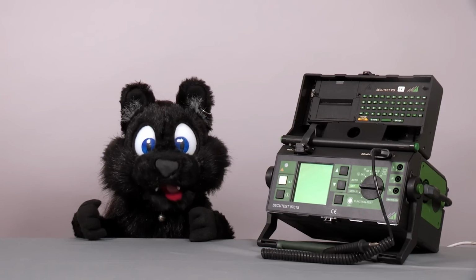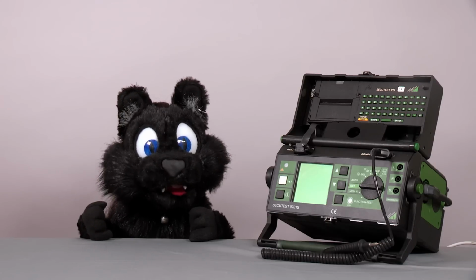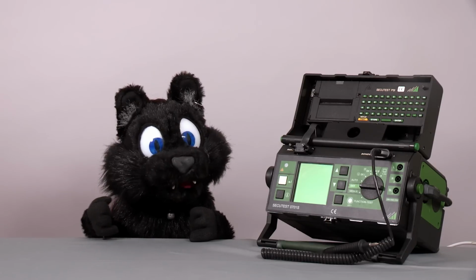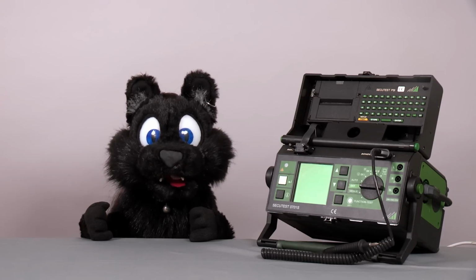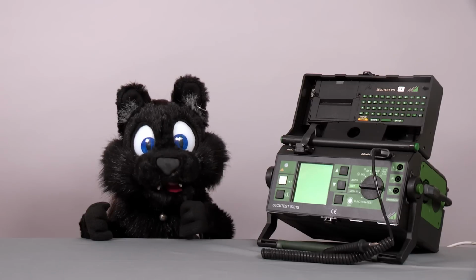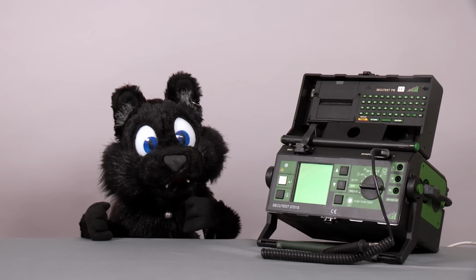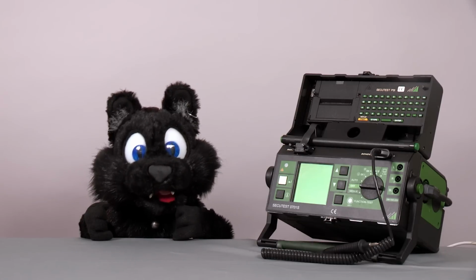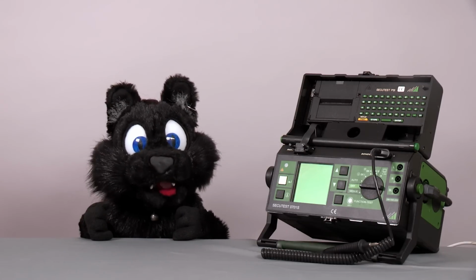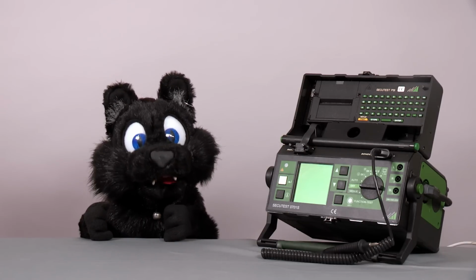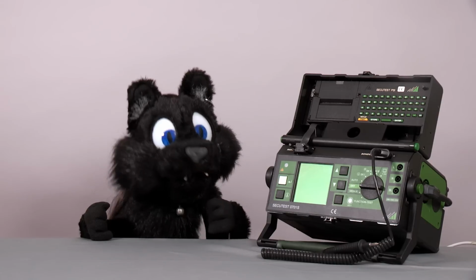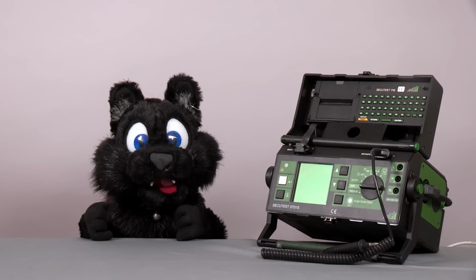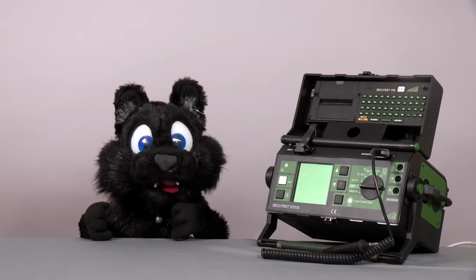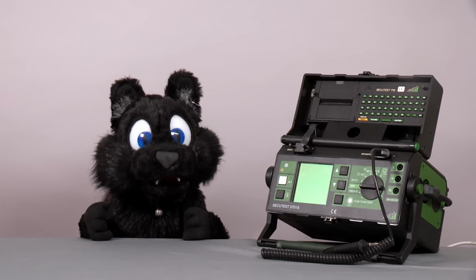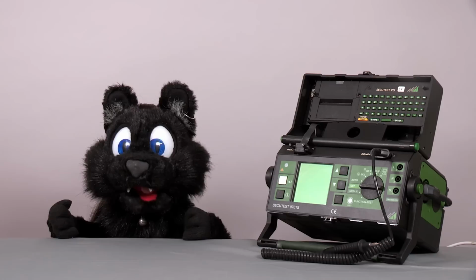In Germany, and therefore most likely similar in most of the EU, electrical appliances that are used in commercial settings like offices, hotels, shops, etc. need to be checked for electrical safety. The details of the test parameters are outlined in two DIN standards, 701 and 702. Similar in content, one is for first-time checks and the other is for repeated checks after repairs.